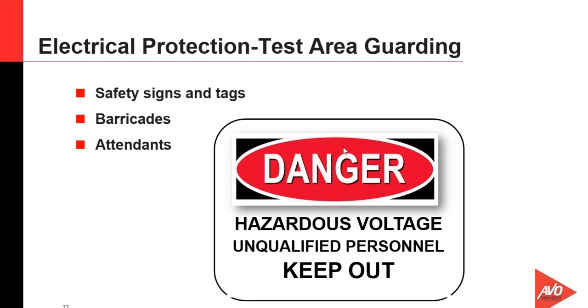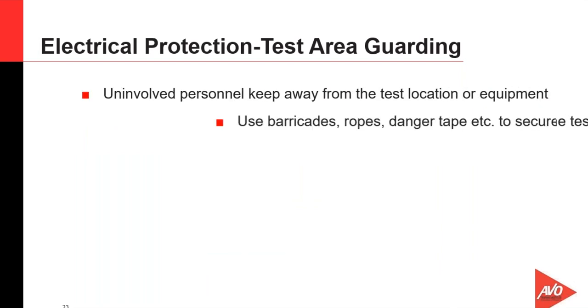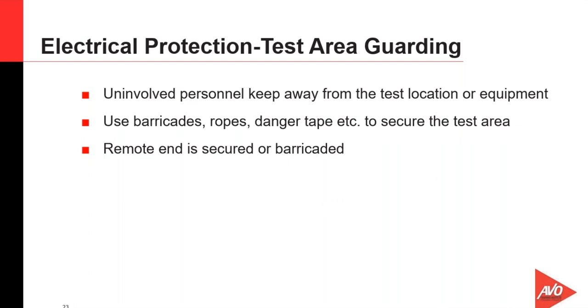This is an ANSI design sign. It does meet the requirements. It says danger. It warns of what is there, hazardous voltage. Gives us an instruction, unqualified persons keep out. In test area guarding, we want to ensure that we keep uninvolved personnel out of the test area or away from the immediate vicinity of the test equipment. Keep in mind that in our test area, we may have exposed live parts, or we may have exposed live parts of the test equipment itself that can actually produce lethal shock. So we need to keep uninvolved, unqualified personnel out of the test area.